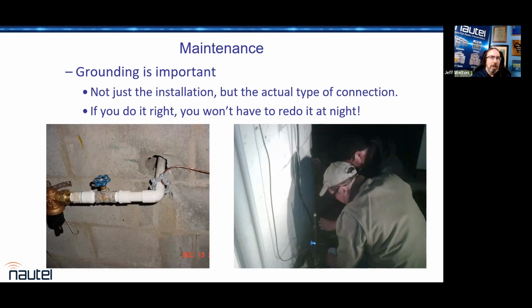But when you're putting big volts on and you put a crimp lug on like a 2 or a 6 gauge wire, give you an example: the Amphenol or Panduit crimp tool we use for the big wires in power transformer connections costs about $5,000 and is hydraulic. So you better have a 200 PSI compressor, that $5,000 tool, and the $500 die for that specific lug, or you're not getting a proper connection.